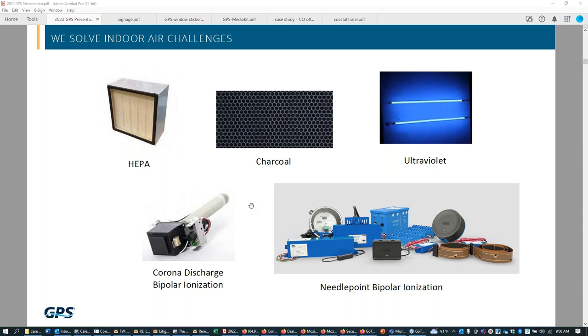And I was doing a lot of parallel research with colleagues, and we did a lot of comparing notes. We studied a lot of different OEMs. We got a lot of different materials from them. And there are two different families of bipolar ionization. The original one is called corona discharge, and that's an ionization that uses a sacrificial component like a glass tube and high voltage electricity to generate the bipolar ionization. Then there is the needlepoint family of bipolar ionization, and instead of having a sacrificial component, it uses a needle, or actually in GPS's case, a bundle of carbon fiber brushes to generate positive and negative ionization.